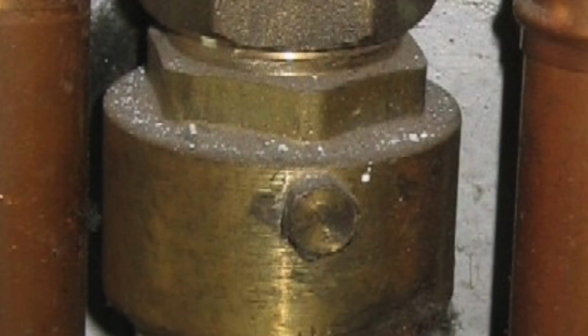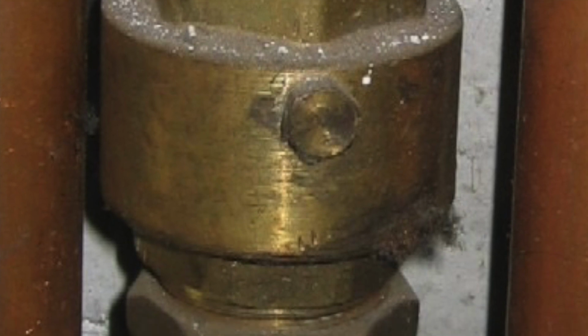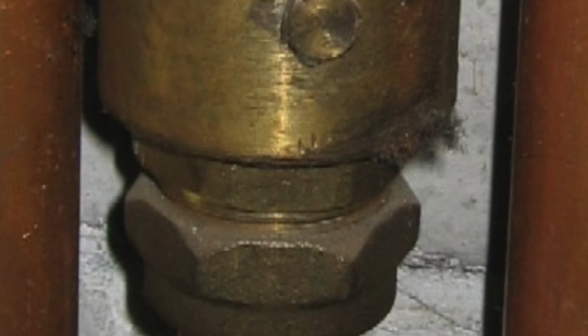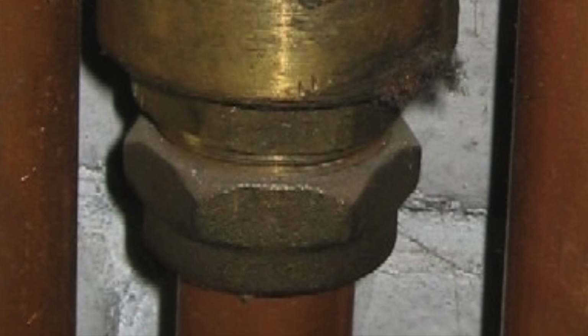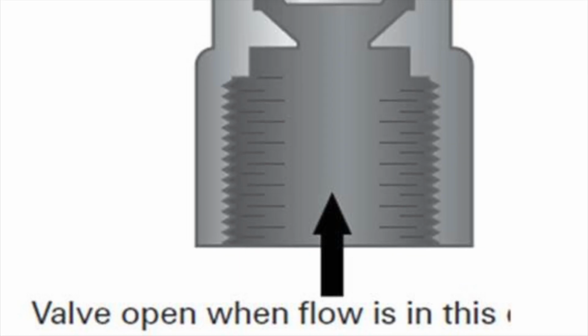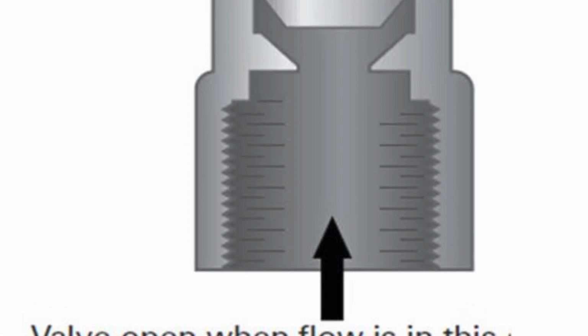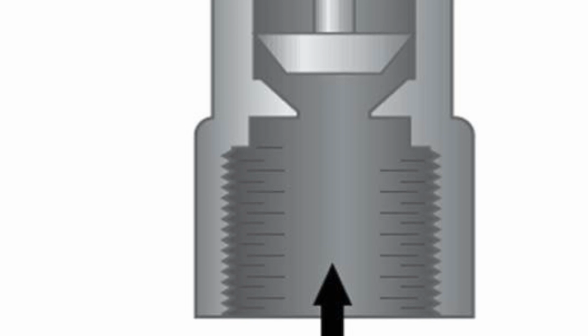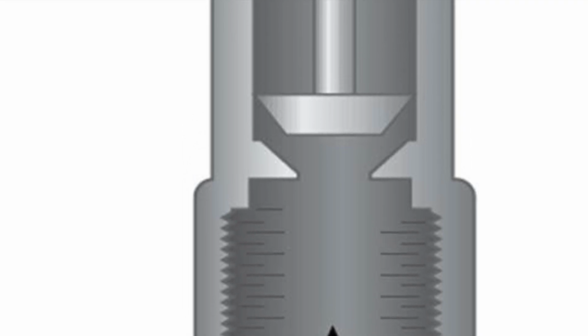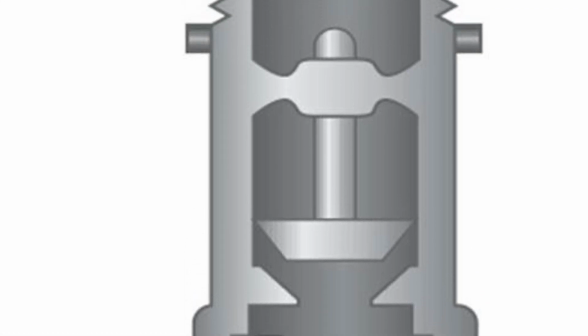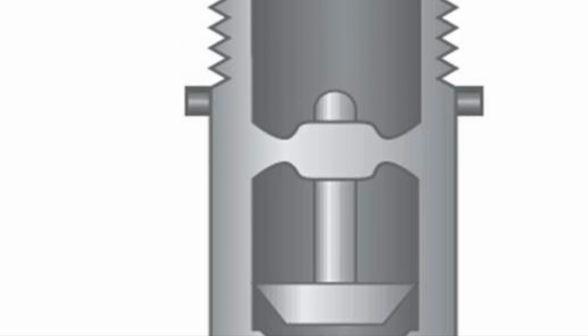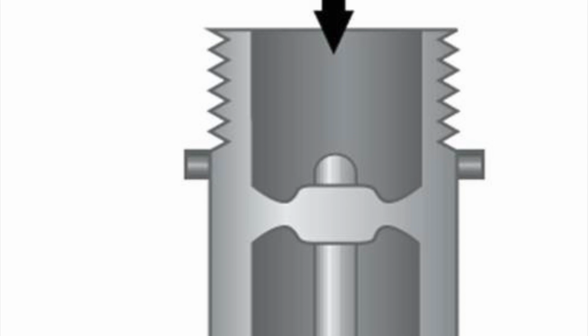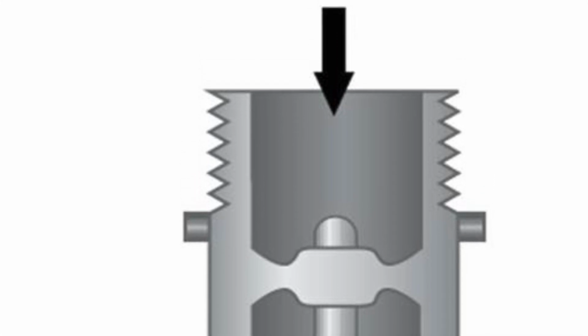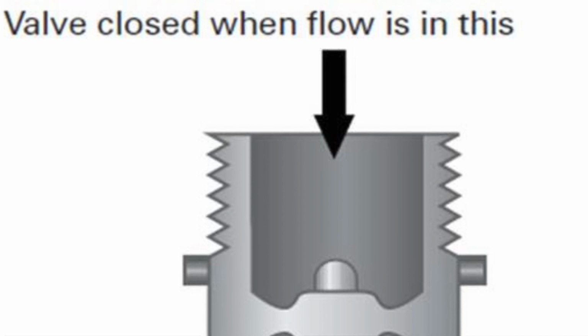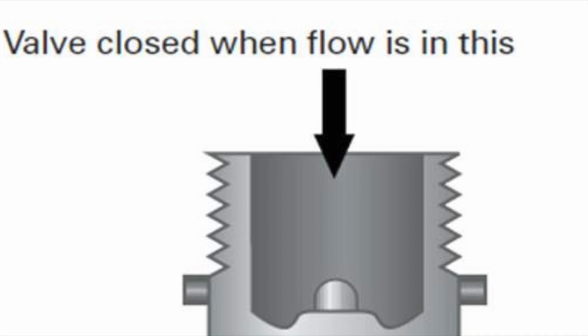They are fitted vertically into the flow pipe of the central heating above the boiler. They are used to stop the water from thermosiphoning into the radiators when the hot water is being called for. So the way this anti-gravity valve works is, under low pressure, the weighted or spring-loaded flap inside the valve will close when the circulation stops in the circuit. This is so that water cannot pass through the wrong way. When circulation of the hot water or heating is needed, the power of the water pump causes the flap or the ball to lift inside the anti-gravity valve to open in order to allow the water to flow through to the radiators. It's as simple as that.